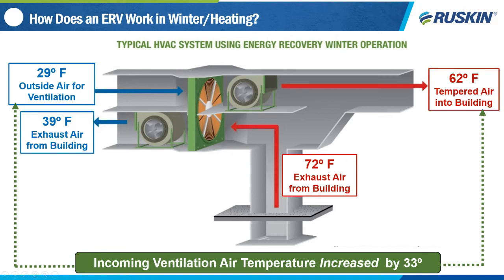That wheel then rotates. The wheel rotates at about 60 RPM. That 29 degree air goes over the nice warm wheel. And instead of bringing 29 degree air into your system, you are bringing 62 degree air into your system. Your ventilation air temp increased by 33 degrees. That's a lot of work for a coil to do. And to get that with a heat exchanger can really benefit your system.